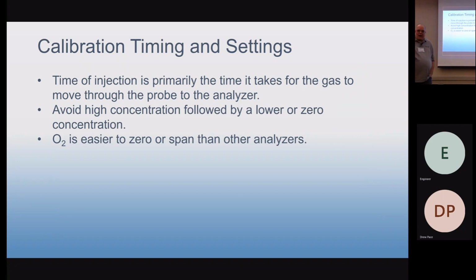But it becomes a challenge when you start going into the more modern philosophies where you use one cylinder to zero. Say you use the O2 cylinder to zero the NOx and CO analyzers, and you use the NOx cylinder to zero the O2 analyzer. So you only have 3 cylinders instead of the 4 cylinders that you would have on this system. You don't really need the nitrogen. There's no reason to have it. So a lot of people have started just doing that. That's the way they do it.